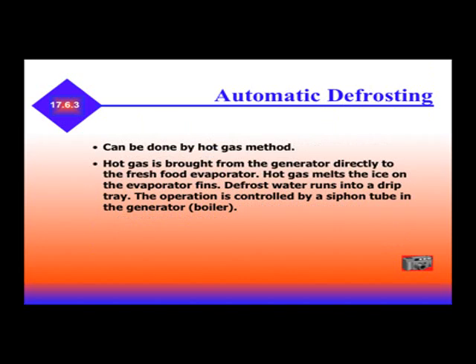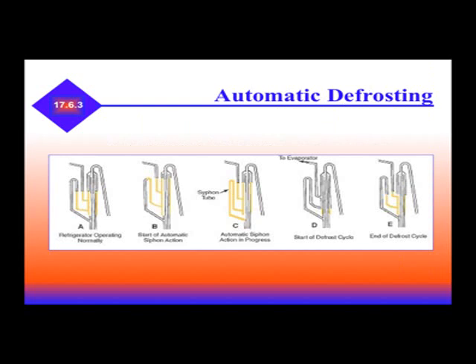Automatic defrosting in absorption systems can be done by the hot gas method. Hot gas is brought from the generator directly to the fresh food evaporator. Hot gas melts the ice on the evaporator fins, and defrost water runs into a drip tray. The operation is controlled by a siphon tube in the generator. In sequence: A — refrigeration operating normally; B — start of automatic siphon action; C — siphon action in process; D — start of the defrost cycle; E — end of the defrost cycle.